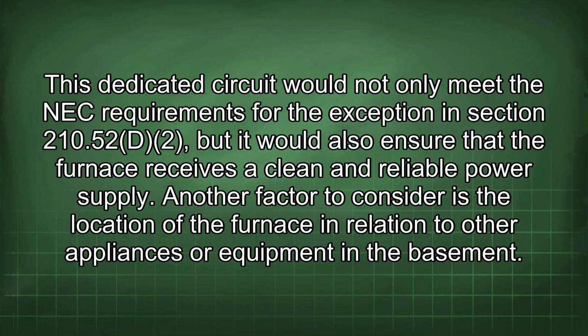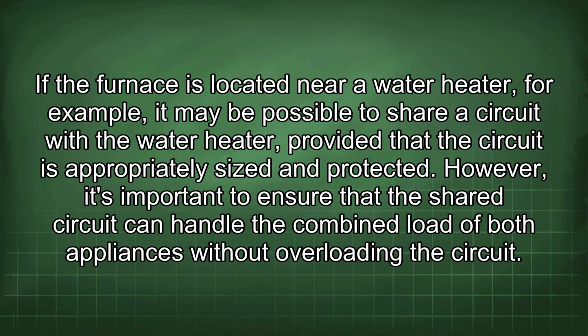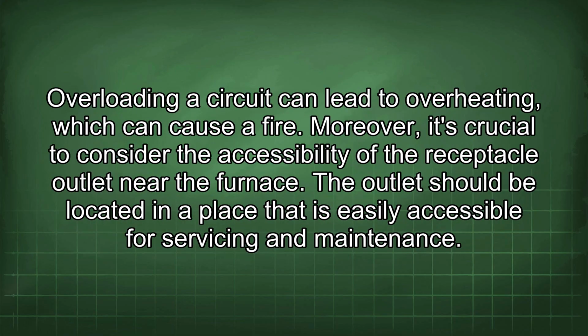Another factor to consider is the location of the furnace in relation to other appliances or equipment in the basement. If the furnace is located near a water heater, for example, it may be possible to share a circuit with the water heater, provided that the circuit is appropriately sized and protected. However, it's important to ensure that the shared circuit can handle the combined load of both appliances without overloading the circuit. Overloading a circuit can lead to overheating, which can cause a fire.